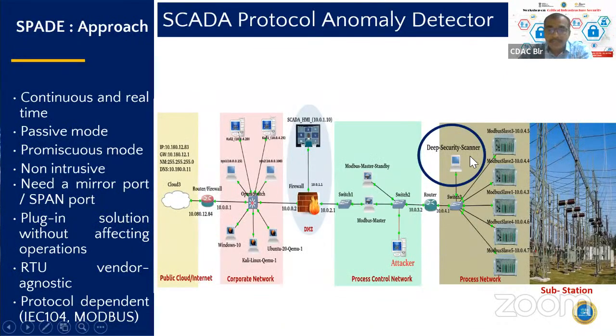Suppose here I am taking the process network. In that process network there are n number of RTUs or PLCs, PMUs, IEDs, whatever interface energy meters will be there. Here we keep one sensor called the deep security scanner, which we call the SCADA protocol anomaly detector. It runs in two modes, mainly by default in passive mode, but it can be enabled for active mode also. In passive mode, it grabs all incoming and outgoing traffic using the mirror port, capturing all the network traffic.